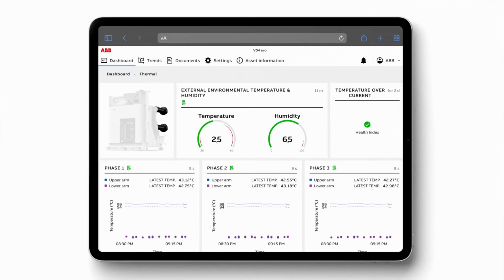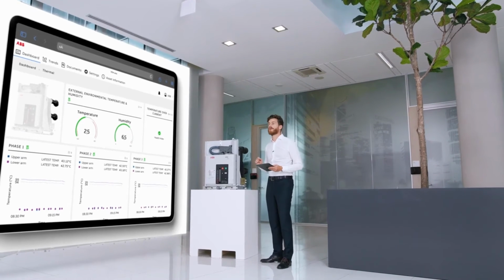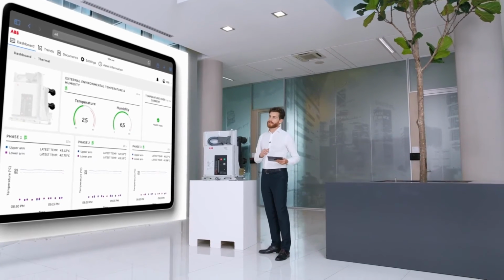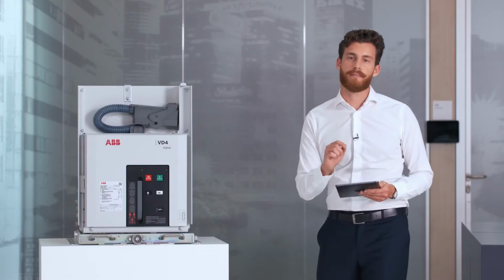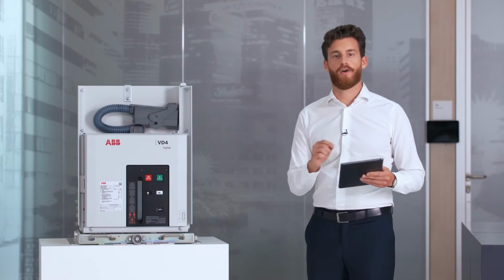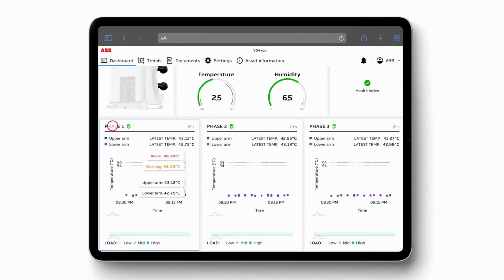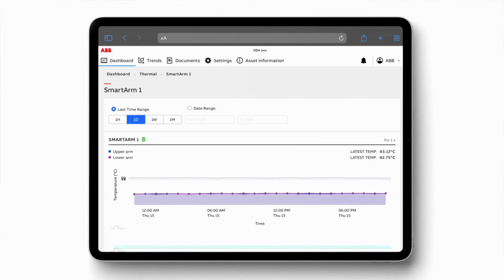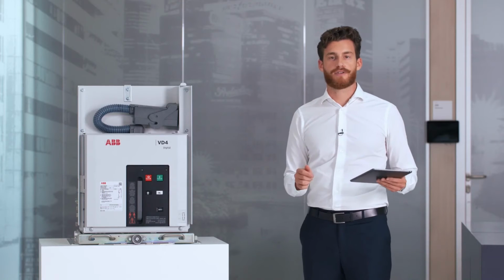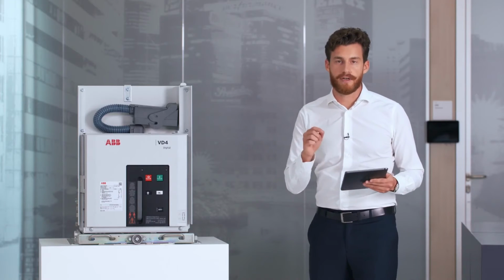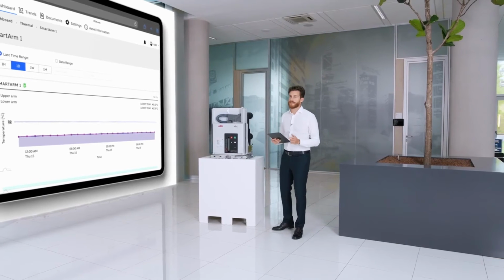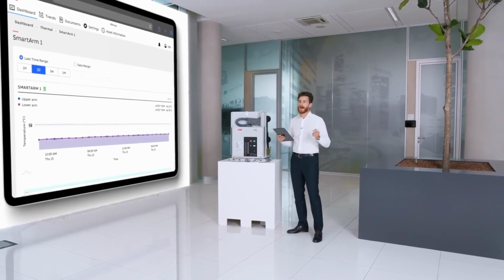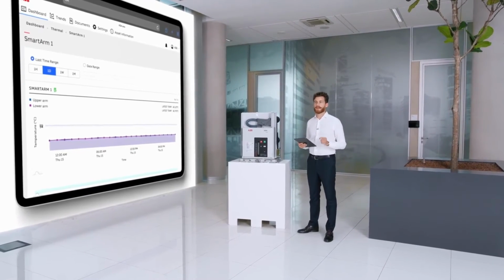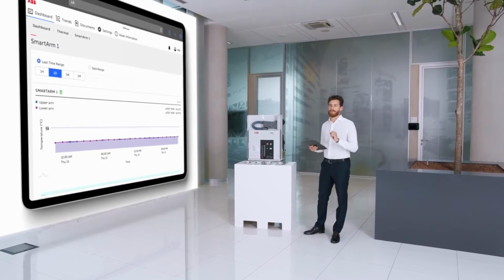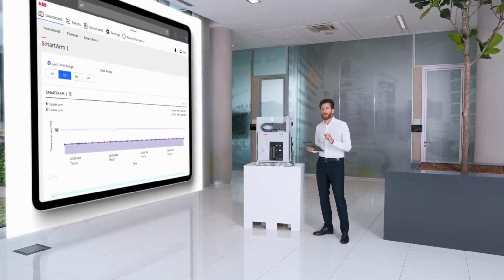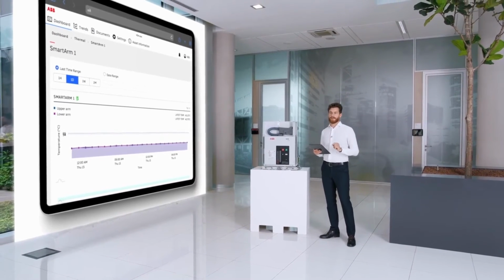For example, the thermal page is where I would go if a loose joint or a damaged contact resulted in abnormal temperature profiles in one or more phases. If not detected properly, they could cause damage to insulating protections or even internal arcs. The combination of data and powerful analytics allows us to provide a dynamic real-time check of the thermal performances, identifying anomalies even at lower current values.